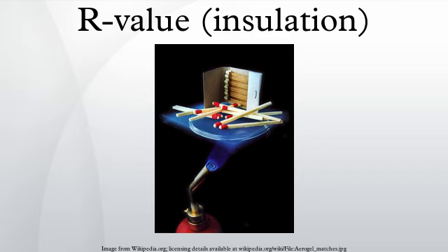Deterioration, insulation aging. R values of products may deteriorate over time. For instance, the compaction of loose-fill cellulose creates voids that reduce overall performance. This may be avoided by densely packing the initial installation. Some types of foam insulation, such as polyurethane and polyisocyanurate, are blown with heavy gases such as chlorofluorocarbons or hydrochlorofluorocarbons. However, over time a small amount of these gases diffuse out of the foam and are replaced by air, thus reducing the effective R value of the product.